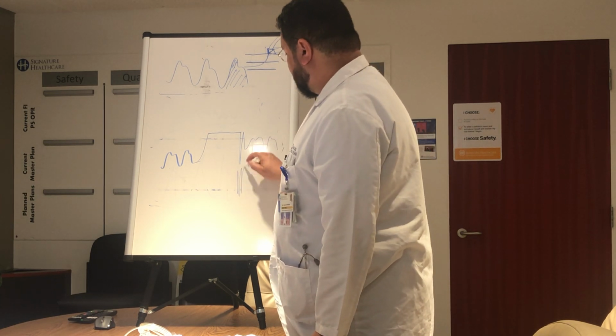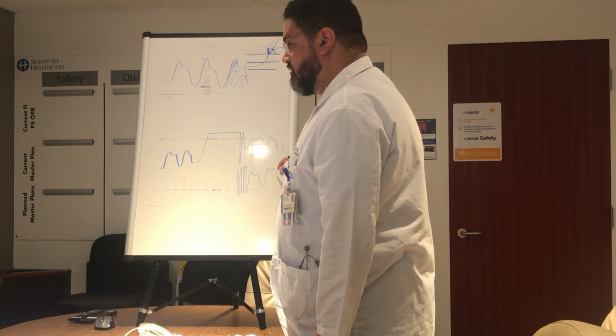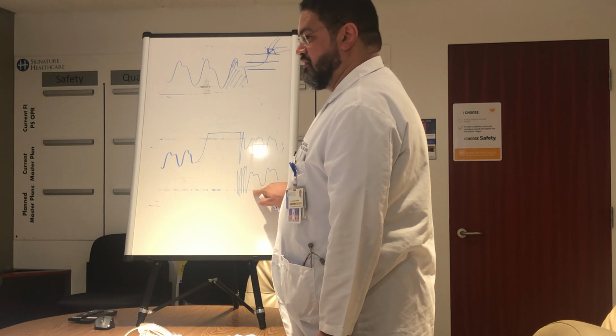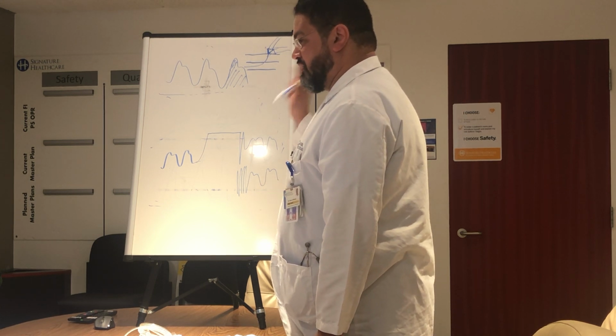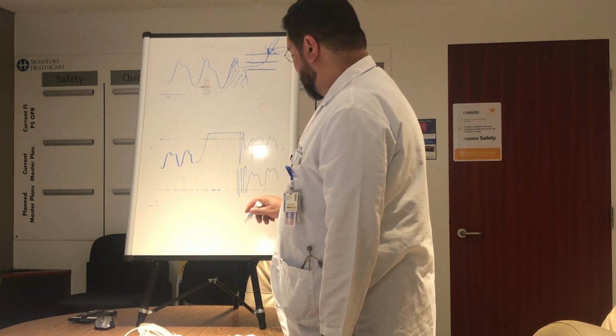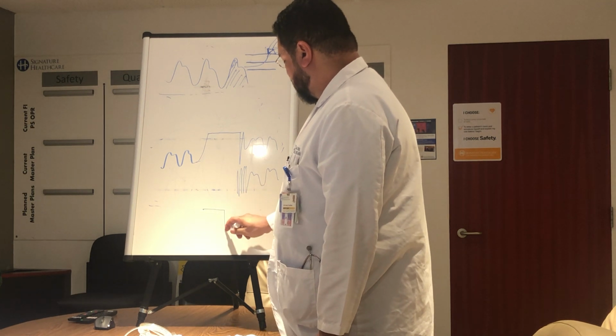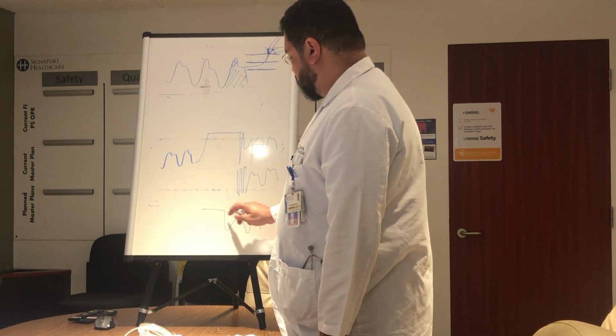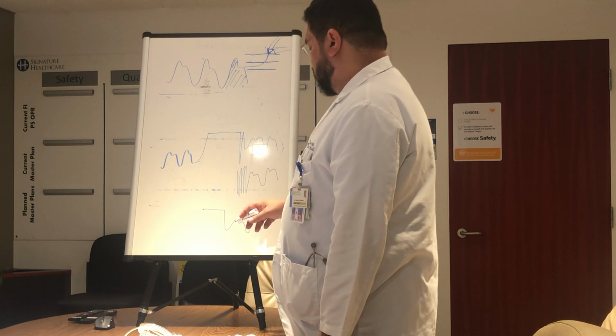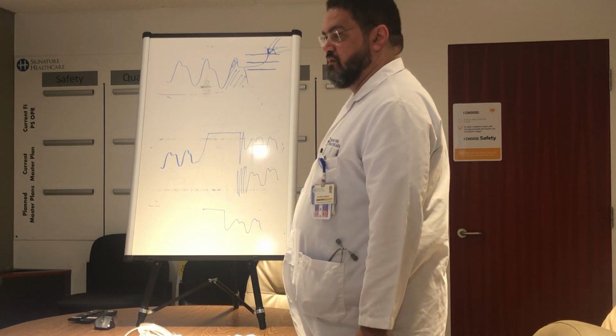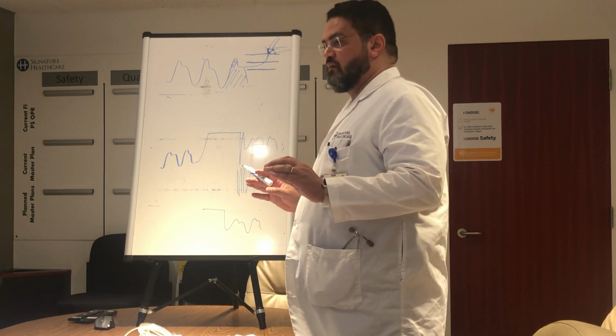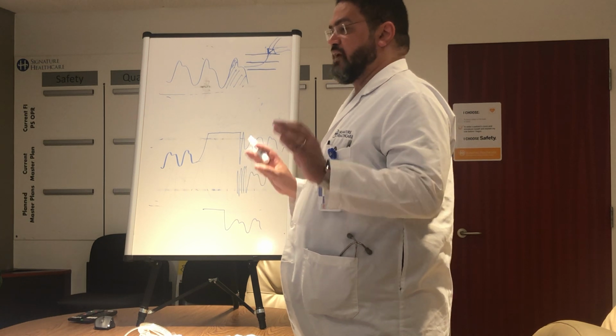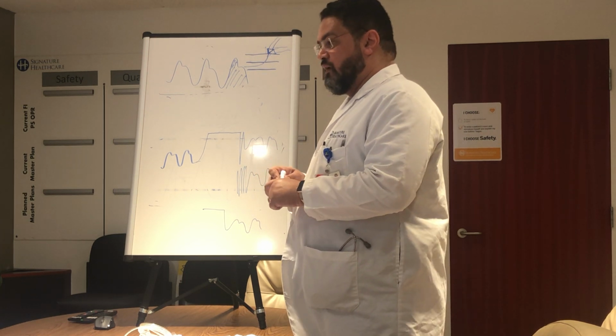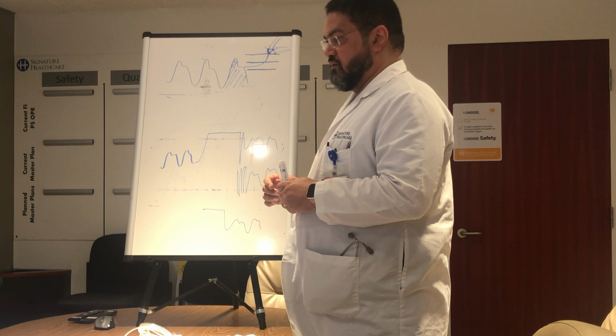If it spikes like this and goes on to measure, that's a hyperresonant A-line. Don't believe it. It's actually measuring higher than it's supposed to. The spike is there. And if it measures like this, no spikes, half a spike, that means it is dampened. And it's very simple. The test can be done in exactly 2 seconds, and you'll know if you should trust your A-line or not.